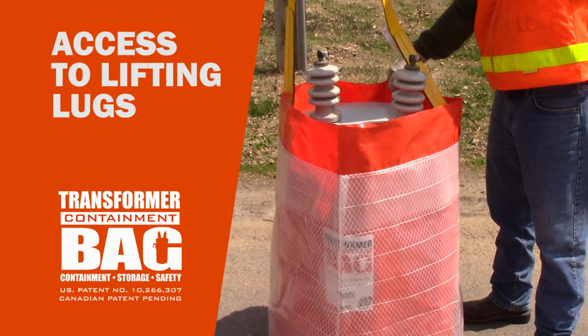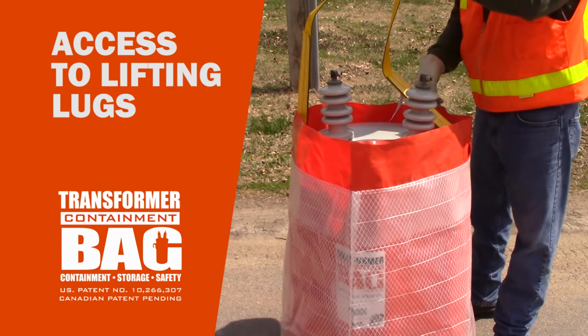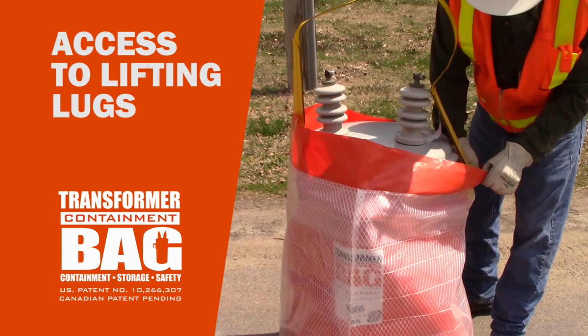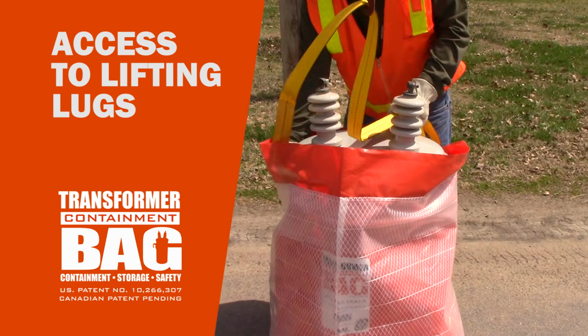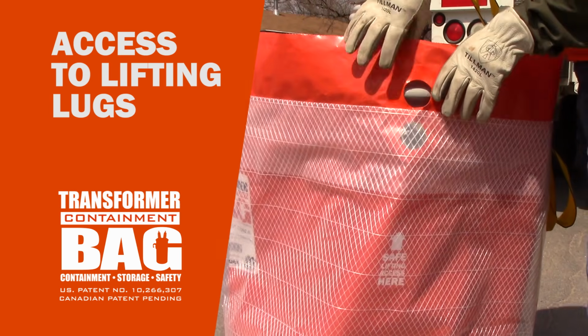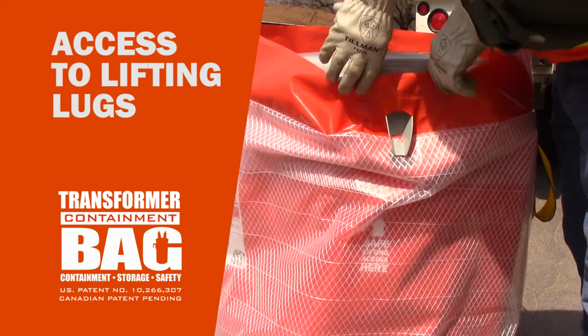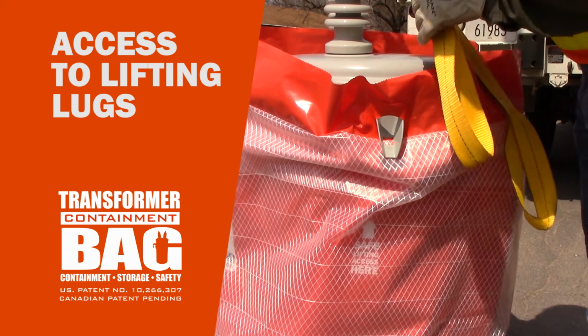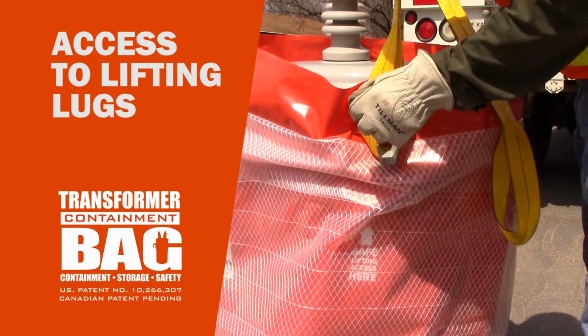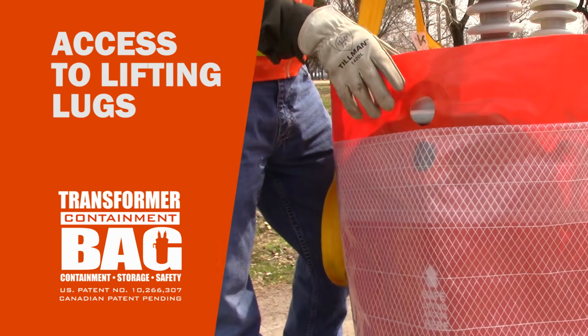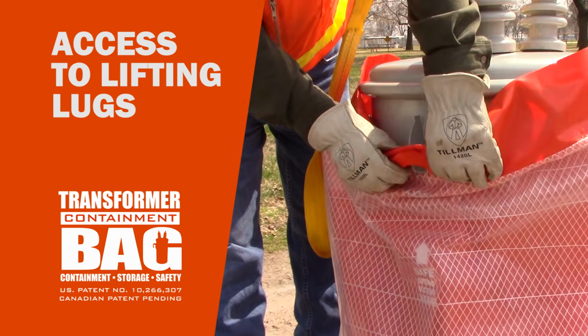After the transformer is safely lowered into the Transformer Containment Bag, remove the straps from the lifting lugs and reattach the straps on the outside of the bag. Repeat this process on the other side.